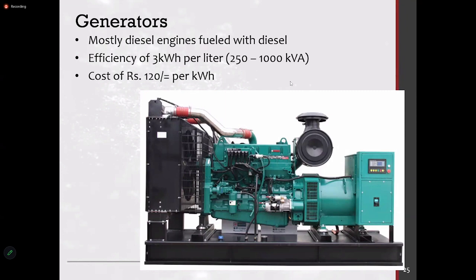You measure the kilowatt hours from the generator and the diesel consumed, and see what the ratio is, just like a vehicle efficiency thing. Roughly it should be in the range of 3, but most of the generators that I have come across are not running at that. The other key issue is that generators should be at least 40% loaded. That is a must on the generator side, otherwise the engine bearings and packings will have issues if your generator is less loaded.